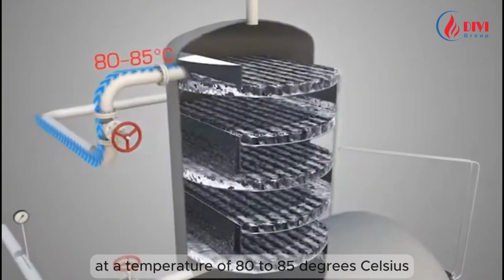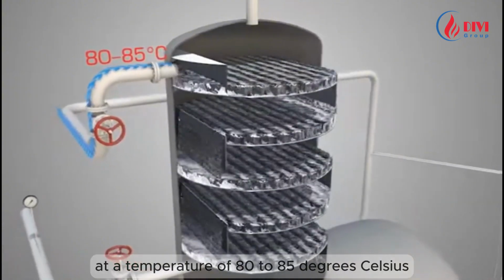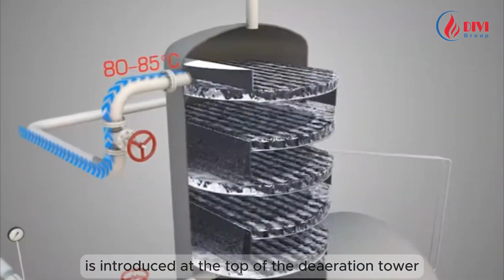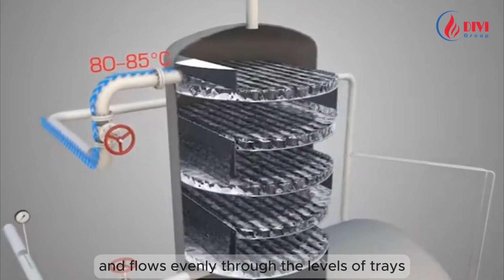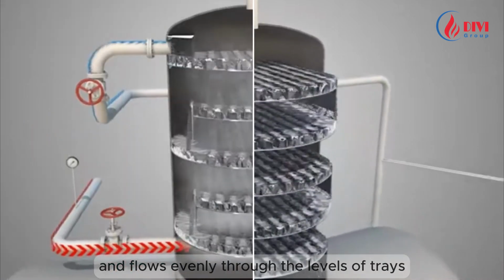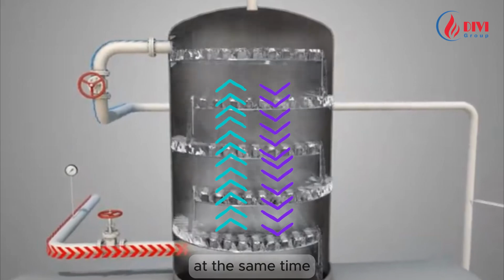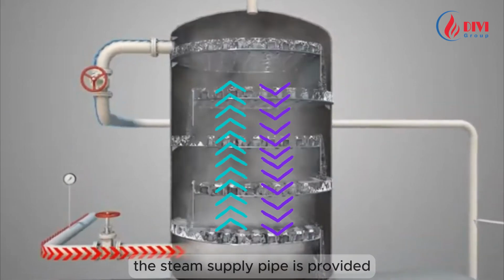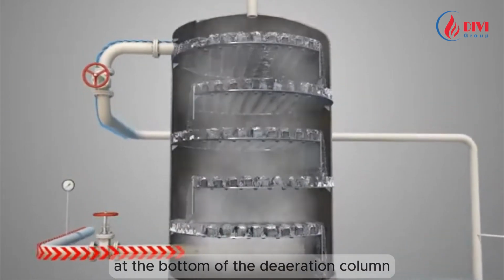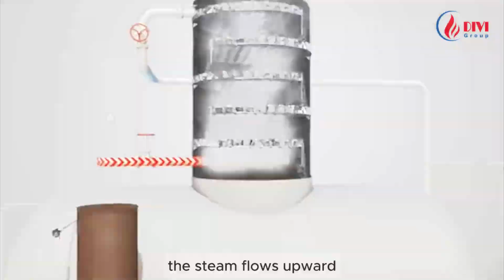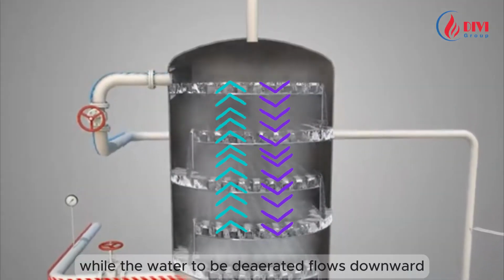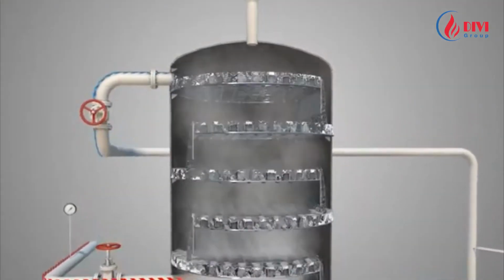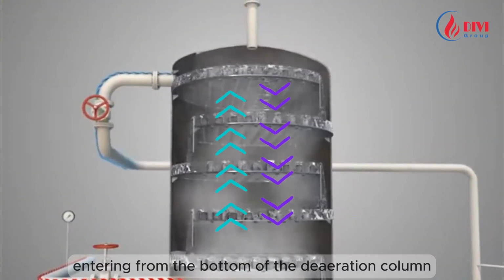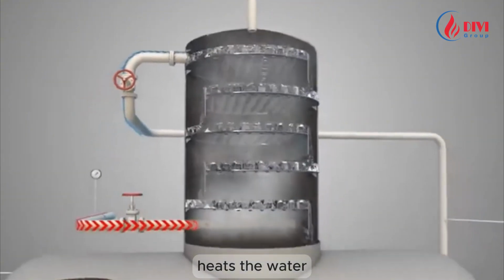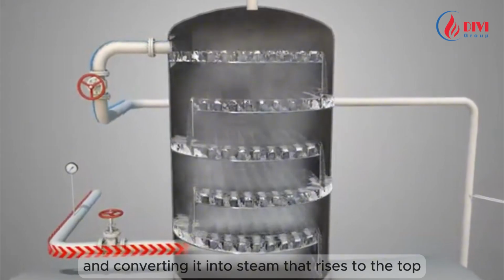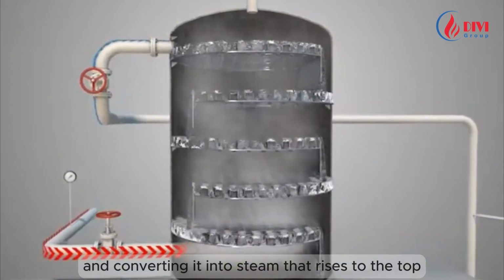Water from the economizer at a temperature of 80 to 85 degrees Celsius, not yet deaerated, is introduced at the top of the deaeration tower and flows evenly through the levels of trays. At the same time, the steam supply pipe is provided at the bottom of the deaeration column. The steam flows upward, while the water to be deaerated flows downward. The heat source entering from the bottom of the deaeration column heats the water, making it hot and converting it into steam that rises to the top.